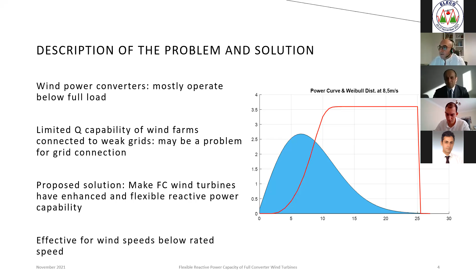Another issue is the limited reactive power capability of wind farms connected to weak grids, which can be a problem for grid connection. Sometimes more reactive power is needed. The proposed solution is to make full converter wind turbines have an enhanced and flexible reactive power capability. I will explain this solution in the next slides. We should keep in mind that this solution is effective for wind speeds below rated speed.